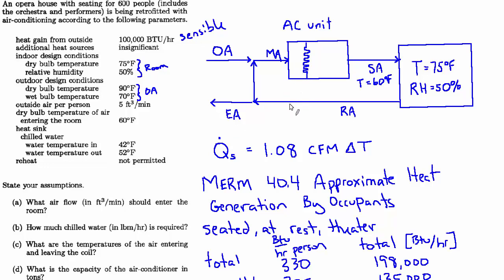What is the air entering the coil? It's a mix of recirculated air, which we can assume is the same temperature as the room, 75 degree return, and then some of that's being recirculated. But that's being mixed with outside air, which is 90 degrees.